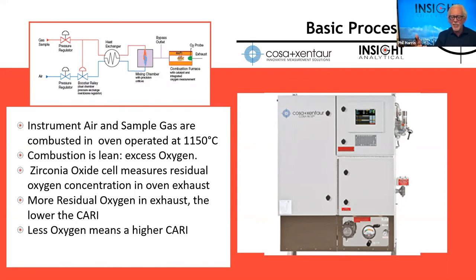If the combustion's lean, there'll be excess oxygen there. The zirconium oxide fuel cell measures that residual excess oxygen. Once we know that excess oxygen, we can calculate our combustion air requirements. The more residual oxygen there is, the lower the combustion air requirement, and less oxygen means a higher combustion air requirement.